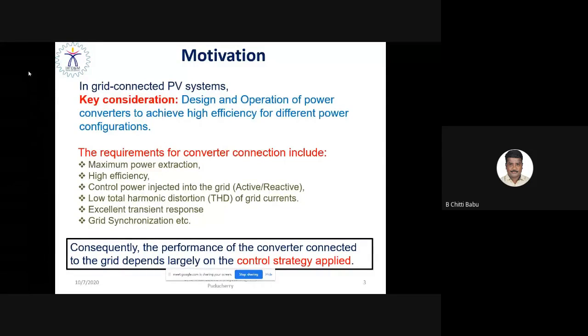And moreover, the power which is being injected into the utility grid is basically an active and reactive power that has to be a controllable one, because the grid needs constant voltage and constant frequency AC power. Of course, constant voltage and constant frequency mean in turn it needs active and reactive power. As you might know, active power control is basically a frequency control, and reactive power control is basically a voltage control, as it needs to have an independent power control that is being injected into the utility grid.